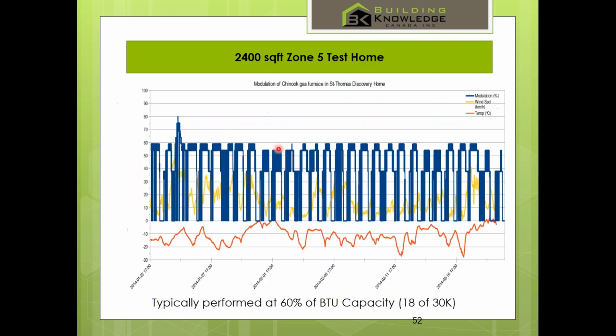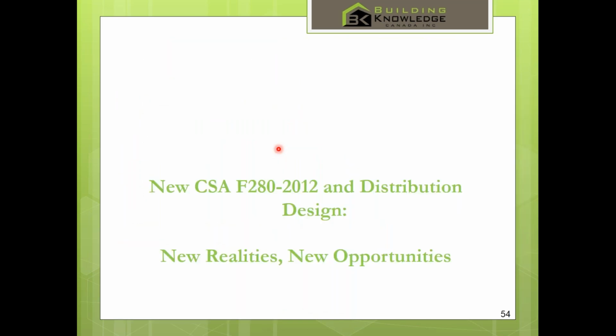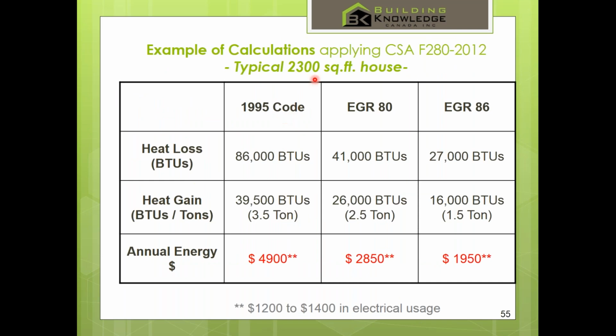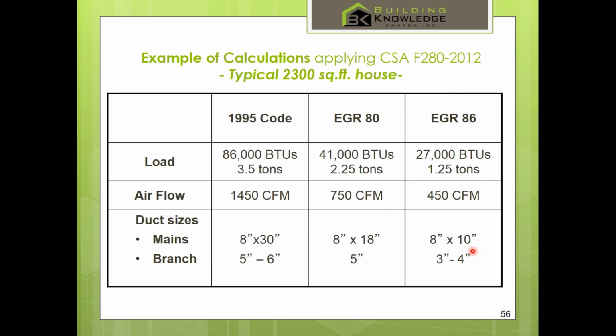I'm going to skip some of this because Michelle's going to show it to you. A couple things I want to bring out. Here's a sample of a 2,300 square foot home, moving to EnerGuide 80 new code, moving to R2000, future Energy Star, net zero ready. You'll see loads drop substantially. You'll see heat gain loads drop as well. It's all good news for the homeowner, but then it gets a little funny for the designers because all of a sudden, we now also see a smaller fan size.